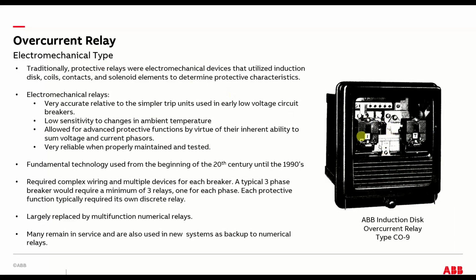This here is your overcurrent relay, electromechanical type. This is an ABB CO9. This goes back for many, many years ago. It was probably in production for maybe 80 years, this thing. This started out as a Westinghouse product, and then when ABB acquired it, now it's ABB. So you might see some old equipment in there with the Westinghouse nameplate, or the ABB nameplate. It's the same relay. We own it, and contact us for information that you need on it.